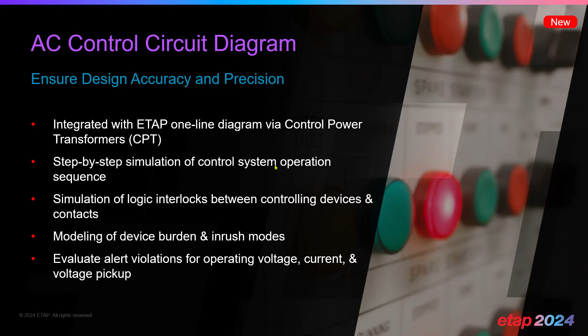an extensive equipment library, and the ability to analyze the operating states of the control devices with a detailed sequence viewer. Within ACCSD, we also do a step-by-step simulation. We are able to simulate the logic interlocks, and we also include the modeling of the device burden and the inrush modes. So quite detailed modeling of every single individual control circuit device, put together into a control circuit diagram, powered by a control power transformer that's ultimately fed by the ETAP single line diagram.